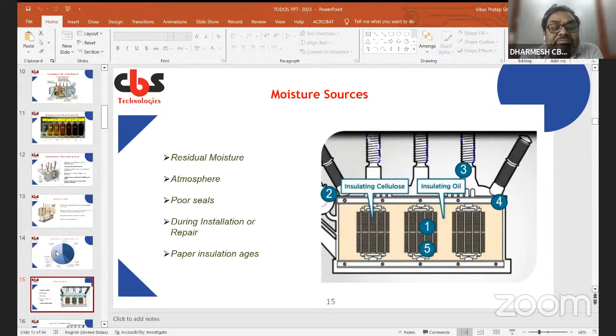Now here you can see moisture in solid insulation. 95 to 99% of the moisture is in the insulation paper. There is constant moisture exchange between paper and oil during temperature transients. As temperature increases, water is released. Moisture deeper in the paper remains rather stable.